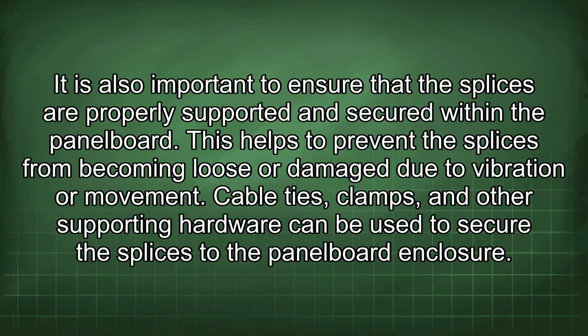It is also important to ensure that the splices are properly supported and secured within the panelboard. This helps to prevent the splices from becoming loose or damaged due to vibration or movement. Cable ties, clamps, and other supporting hardware can be used to secure the splices to the panelboard enclosure.